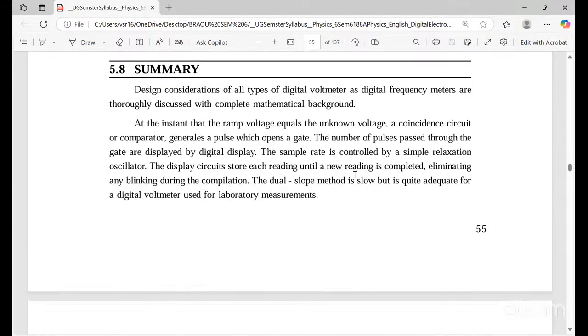This is the summary here. All types of digital voltmeters and the digital frequency meter have been thoroughly discussed. At the instant that the ramp voltage equals the unknown voltage, the coincidence circuit or comparator generates a pulse which opens the gate. The number of pulses passed through this gate is displayed by the digital display, and the sample rate is controlled by the sample rate control. The dual slope method is also slow, but it is quite adequate for a digital voltmeter used in the laboratory.